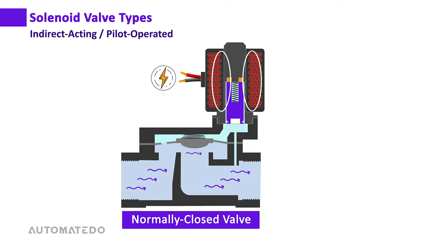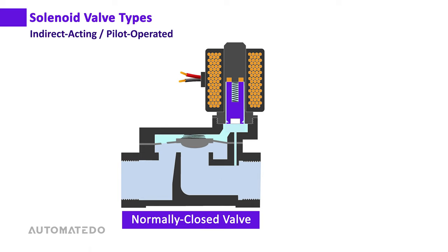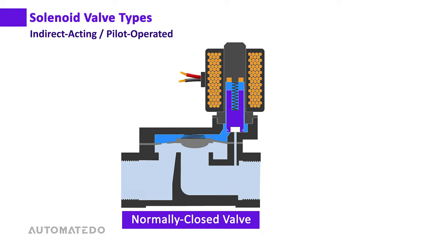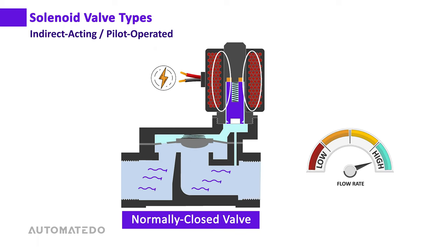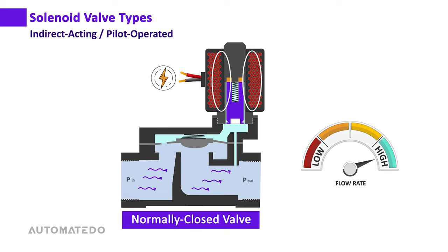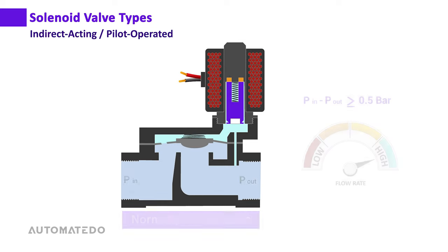As a result, the diaphragm is raised, allowing media to flow freely from inlet to outlet. When the solenoid is de-energized, the plunger falls due to spring force, closing the pilot orifice. Pressure accumulates in the upper chamber, shutting the valve again. The indirect acting solenoid valve is used in high flow rate applications and requires a minimum differential pressure of around 0.5 bar between inlet and outlet.